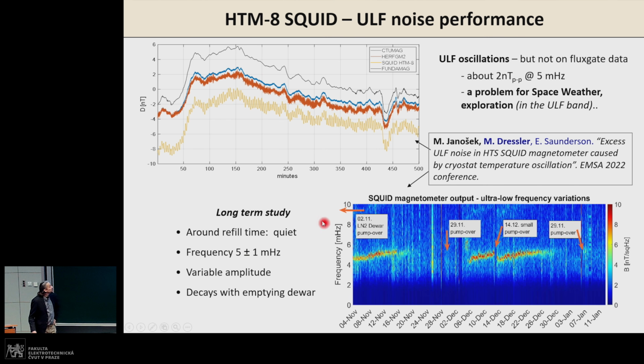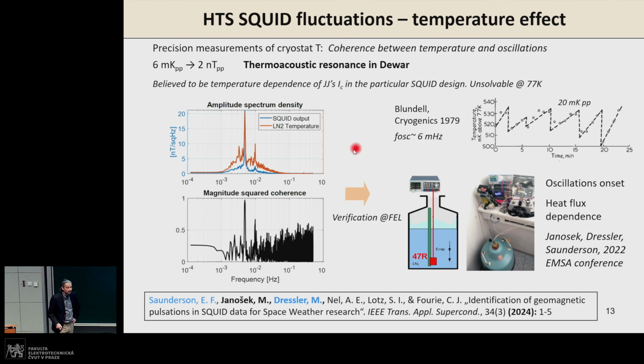measure. We did a long-term study, and we have actually found that this effect diminishes as the dewar goes empty and starts only a few days after we refill the dewar again with liquid nitrogen. So basically, it had to correspond somehow with the liquid nitrogen cryostat and with the dewar properties. We have found almost perfect coherence between the SQUID output and the dewar bath temperature. Of course, it's not perfectly 77 Kelvin. There are also fluctuations, and we were able to monitor those fluctuations with very high precision.